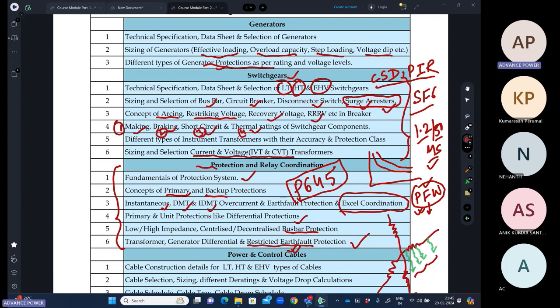These are applicable in LT switchgears also, LT breakers also. We'll even discuss them for the contactor. So for the contactor also we discuss these parameters, and for switchgears and breakers also we discuss these parameters. In detail, we will discuss the asymmetric components of the fault current, in which we have symmetrical and DC components also. Based on that, we derive the making current and breaking current. I will explain in that chapter in detail on which region your circuit breaker is operating and what that region is.